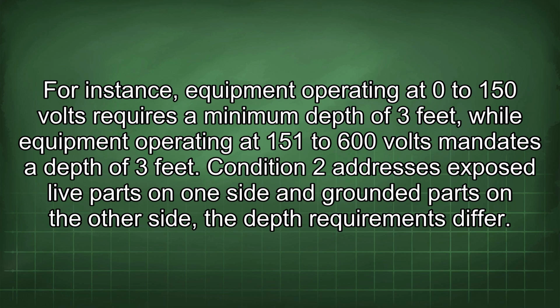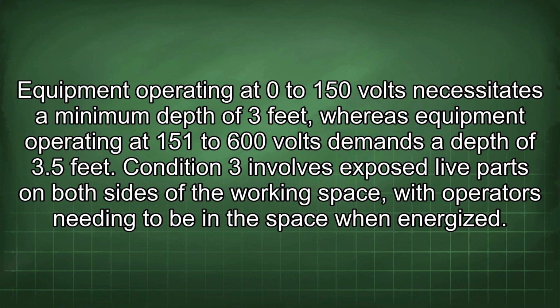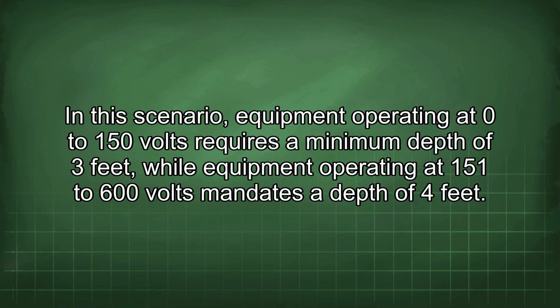For instance, equipment operating at 0 to 150 volts requires a minimum depth of 3 feet, while equipment operating at 151 to 600 volts mandates a depth of 3 feet. Condition 2 addresses exposed live parts on one side and grounded parts on the other side. The depth requirements differ. Equipment operating at 0 to 150 volts necessitates a minimum depth of 3 feet, whereas equipment operating at 151 to 600 volts demands a depth of 3.5 feet. Condition 3 involves exposed live parts on both sides of the working space, with operators needing to be in the space when energized. In this scenario, equipment operating at 0 to 150 volts requires a minimum depth of 3 feet, while equipment operating at 151 to 600 volts mandates a depth of 4 feet.